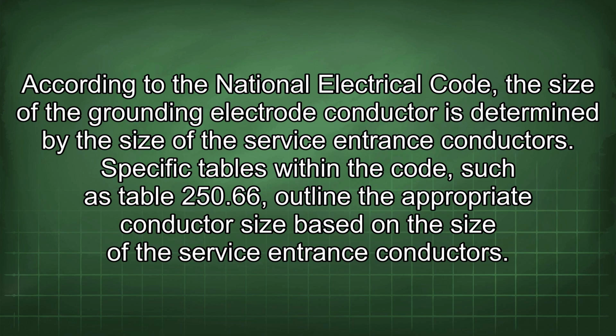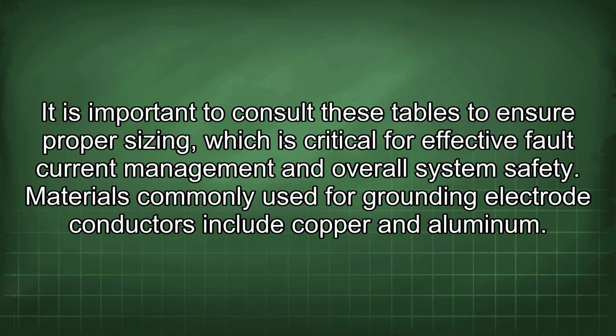According to the National Electrical Code, the size of the grounding electrode conductor is determined by the size of the service entrance conductors. Specific tables within the code, such as Table 250.66, outline the appropriate conductor size based on the size of the service entrance conductors. It is important to consult these tables to ensure proper sizing, which is critical for effective fault current management and overall system safety.